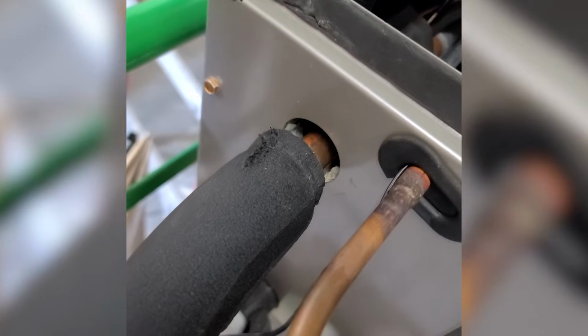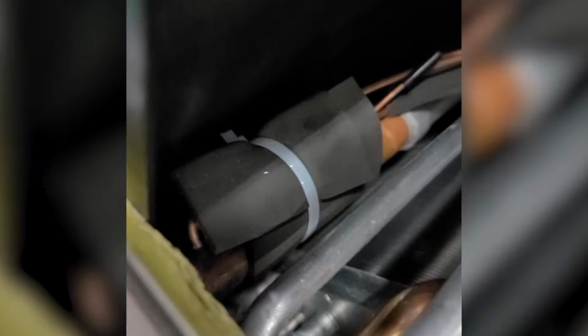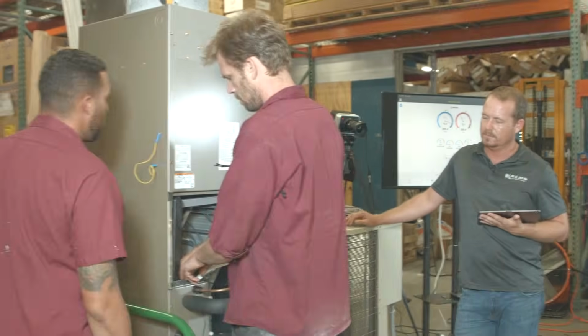The bulb is actually factory strapped with a zip tie. I've never seen that before. Maybe there's another strap underneath that? Inside, there's another one on the inside. Okay, all right. But this was open, so it's sucking air in, which could be affecting it and causing it to overfeed. So we're going to seal that up and see if that fixes the problem.